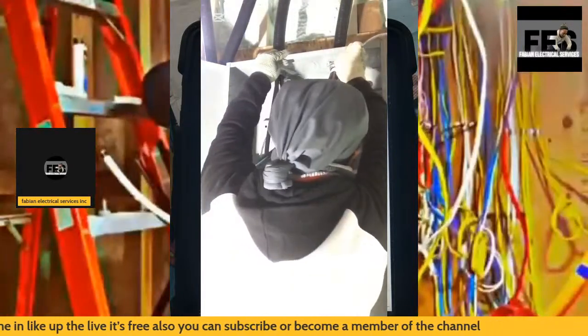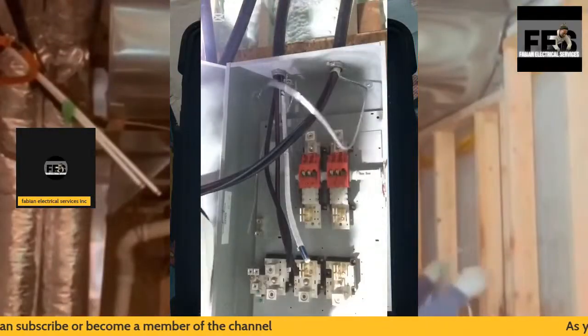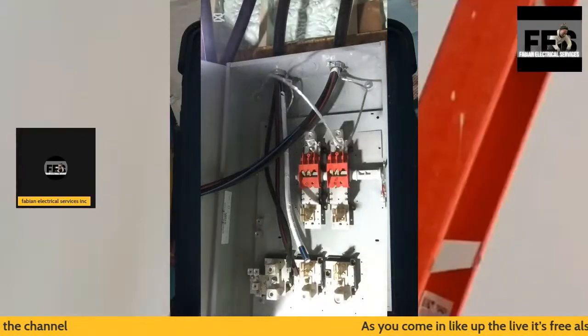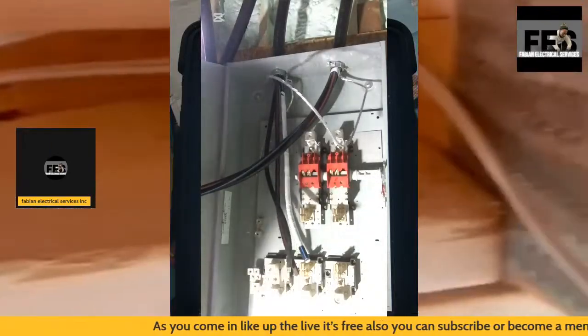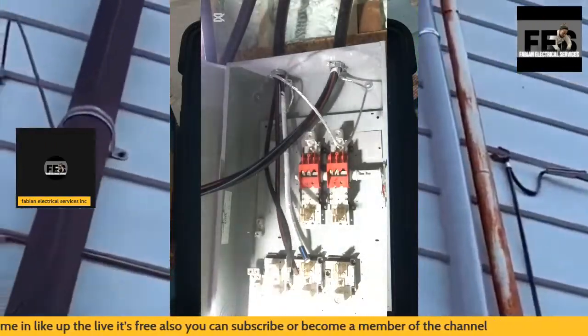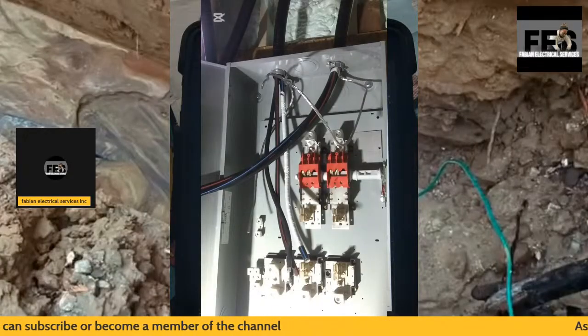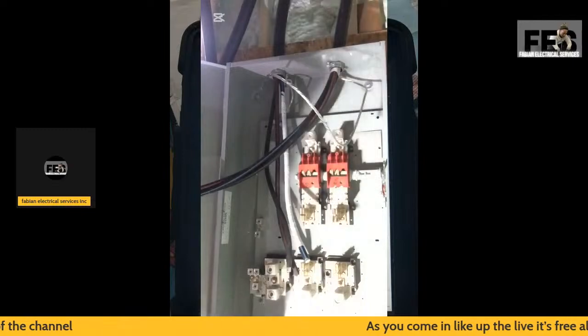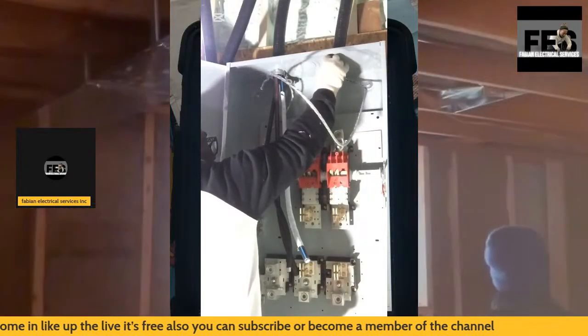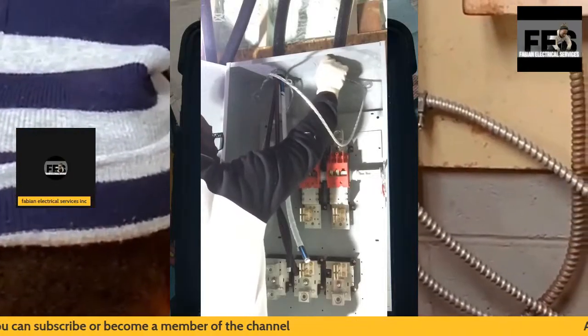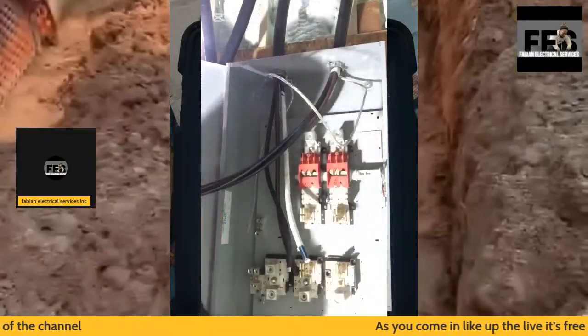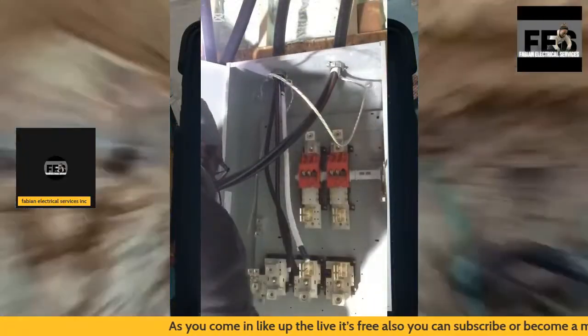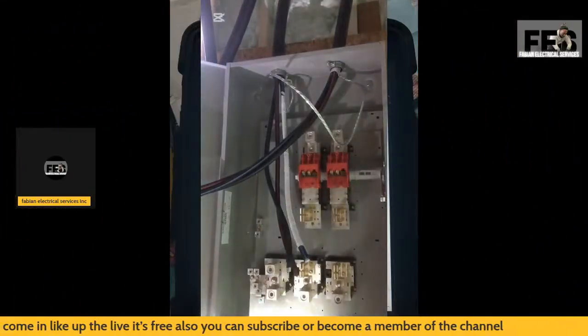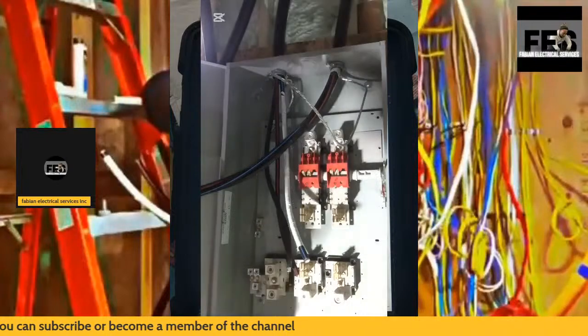Also, you're going to see I have my phasing tape on my cable. The reason is this cable does not come with an identified neutral, and the code book states that your incoming neutral has to be identified. There is an electrical code rule that states that for a particular size of cable we must identify it. So this is what I am doing here, identifying my conductors with the white tape that is being used. It's always best to have your line and loads coming in separated. Never have them touching each other. It is a code compliance rule that states that your main feed coming in is not supposed to come in contact with your actual load side going out. So for this reason, you're going to see the installation.